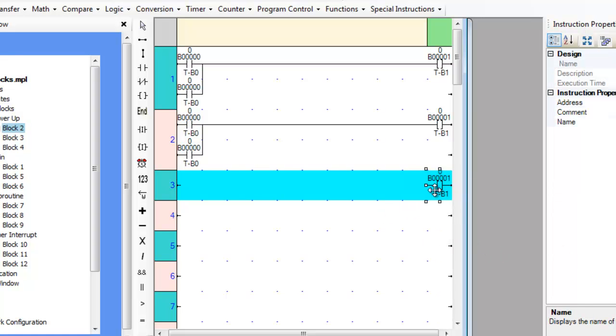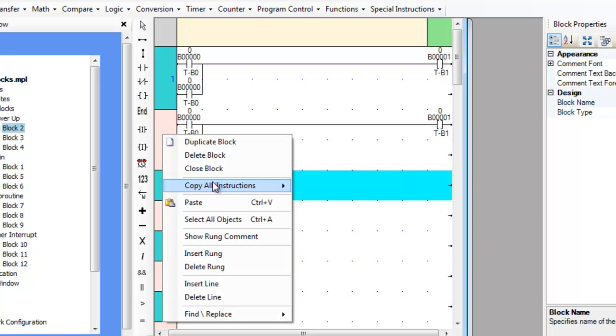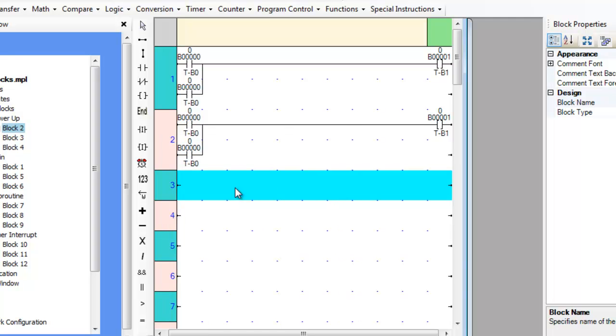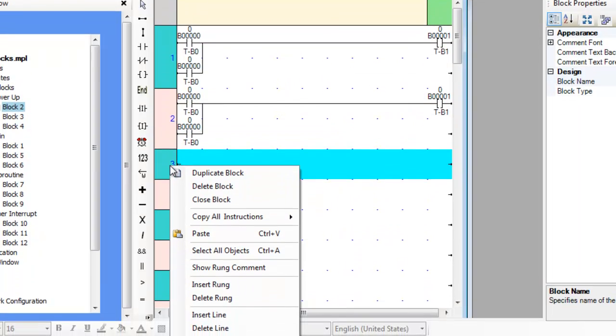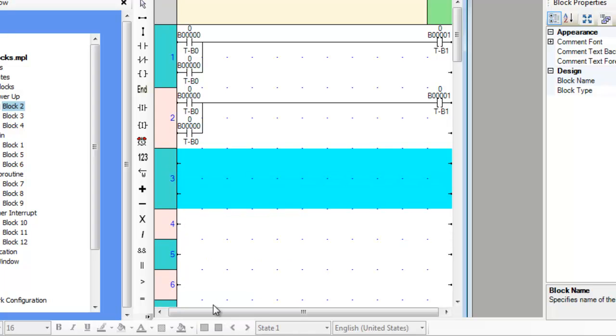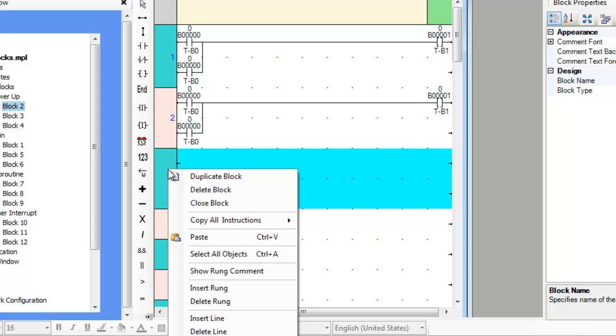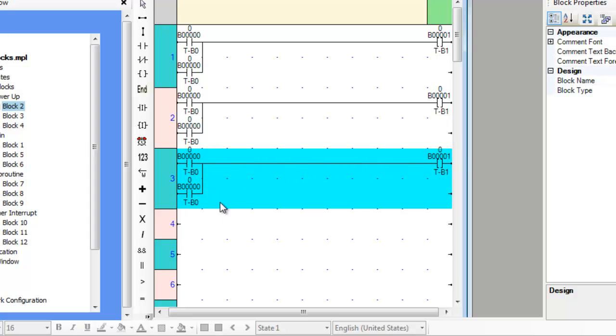To copy and paste a rung, right-click on the numbered area to the left of the rung and select Copy All Instructions. A choice is presented to copy the rung or the selected line of the rung. Select Rung, then right-click on the numbered area where the rung is to be copied. If the rung requires more lines than are present in the blank rung, select Insert Rung and Insert Line to create the space required, then right-click on the numbered area and select Paste.